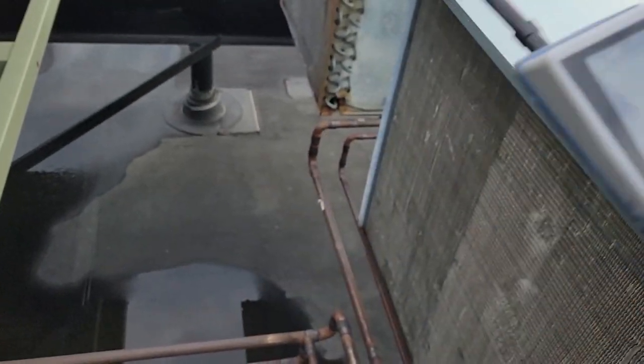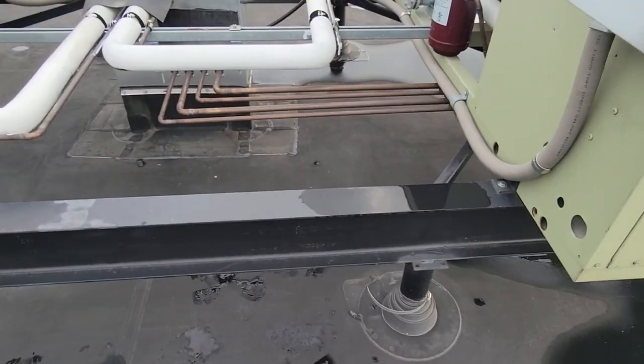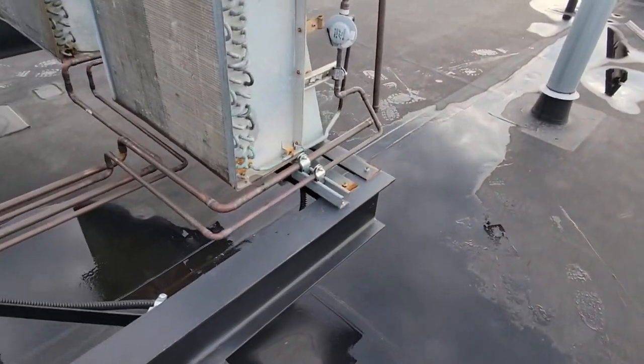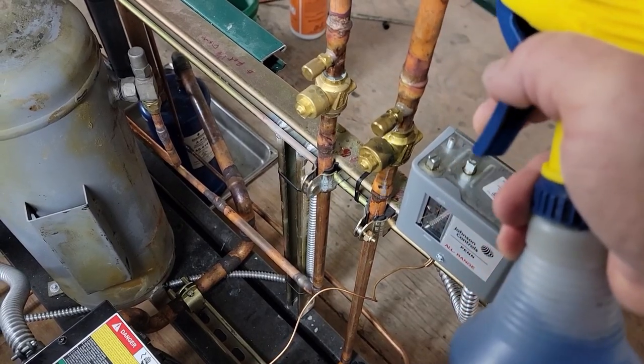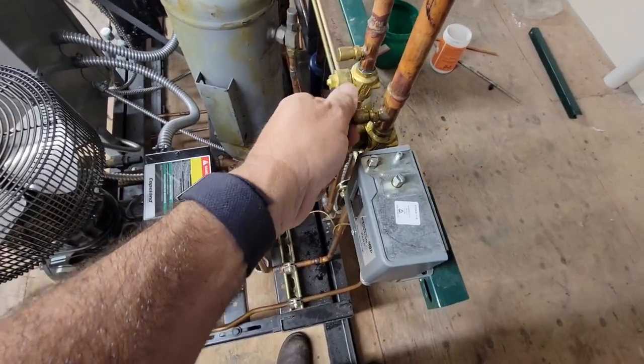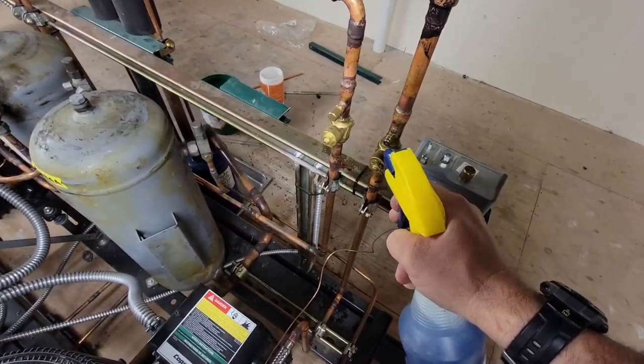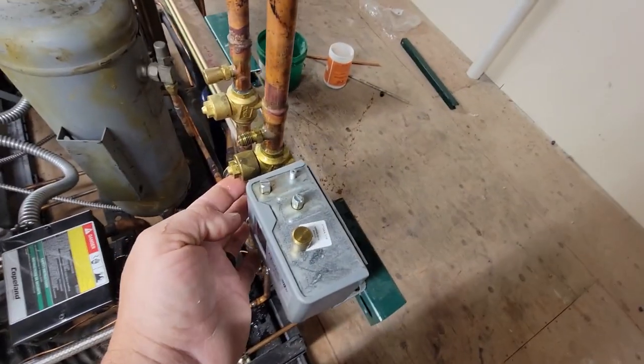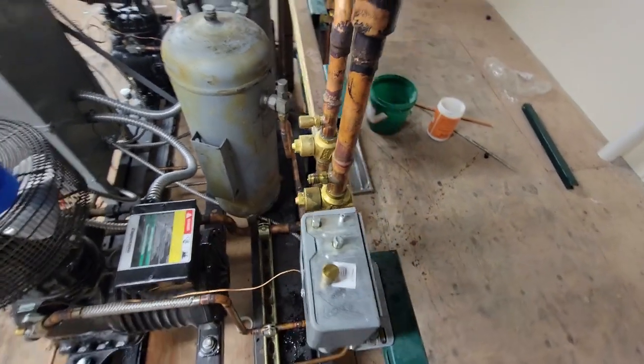You can see they've already made one repair right there, so it's very probable there are other places on some of these. This isn't a huge rack — I bet it's got probably 35 or 40 pounds in it maybe. This is after I tightened it; the unit's not even running. That's as tight as I can get it. I'm not big into spraying solution into the valve core, but oh my gosh — that thing's blowing out of there. That is ridiculous.